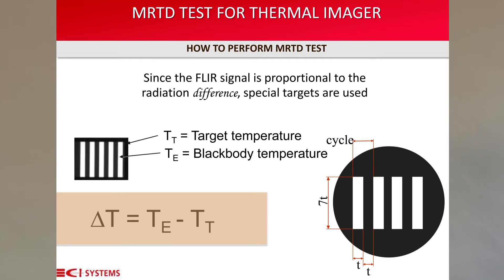To run the MRTD test, we first have to understand the idea behind thermal imaging. Thermal cameras are sensitive to the temperature difference of objects captured within the field of view of the camera. This ability to distinguish objects is linked to the thermal and spatial performance of the camera. A four-bar target's spatial resolution simulates the size of the object. The target's temperature along with the background temperature generated by the blackbody simulates the contrast difference between the object and the background. The delta T measured in the test is the temperature difference between the target temperature and the blackbody's temperature.